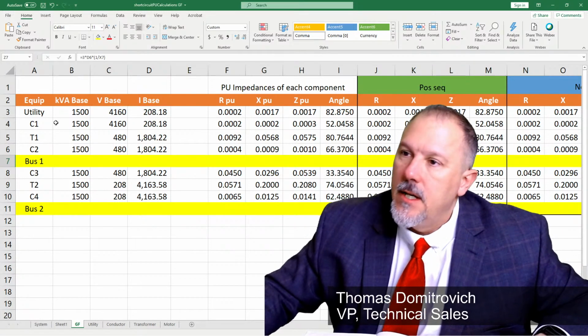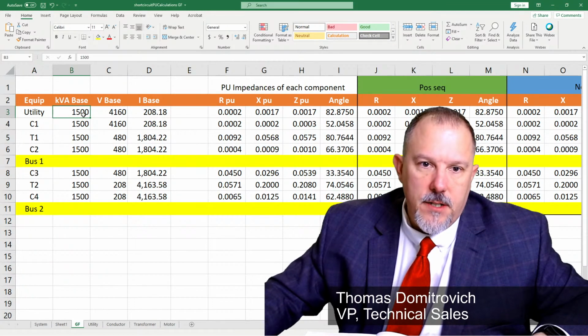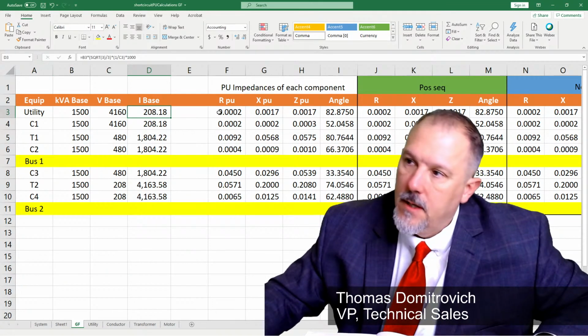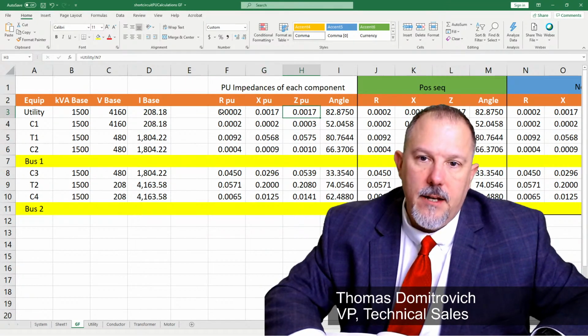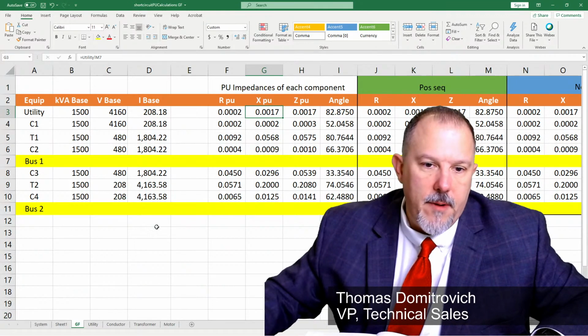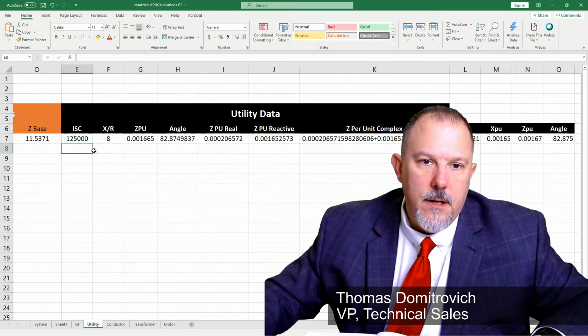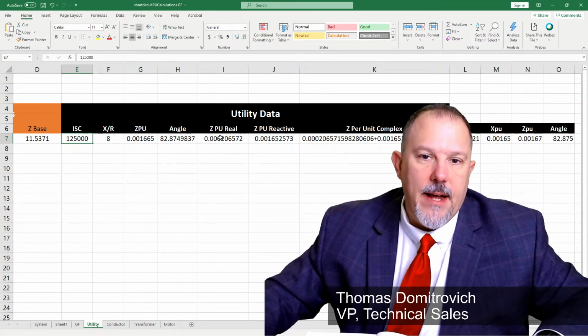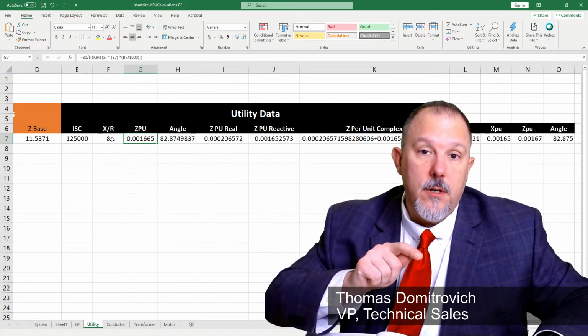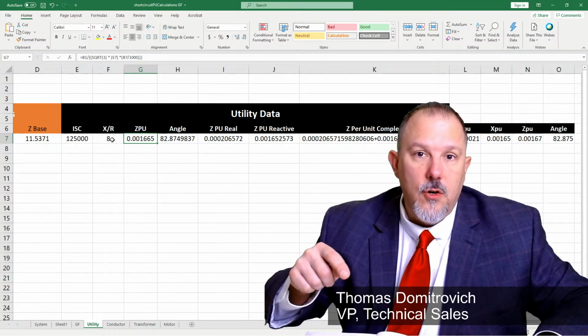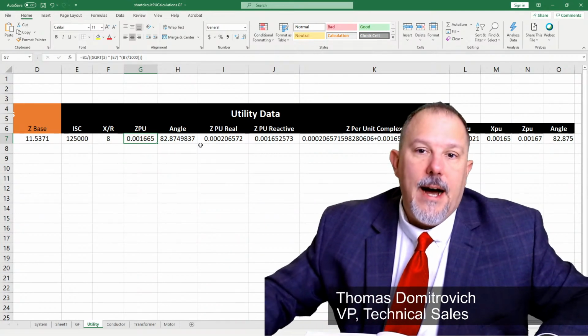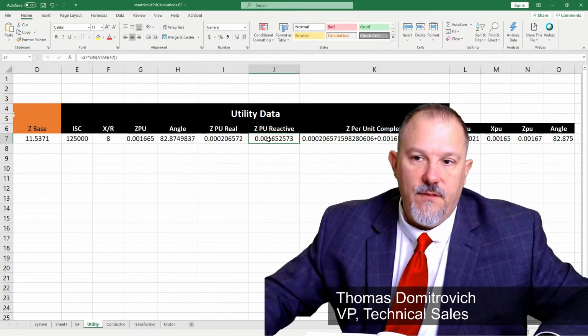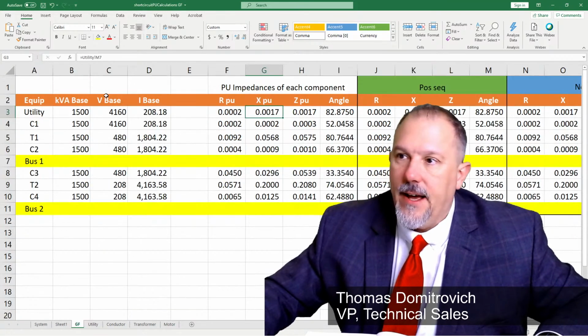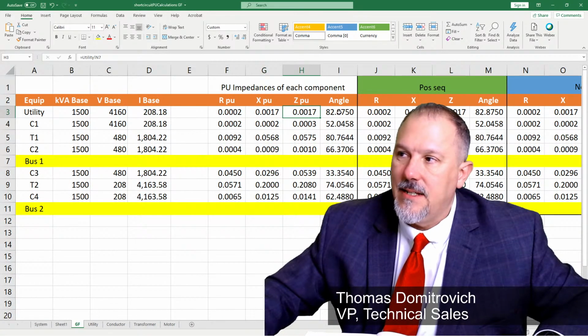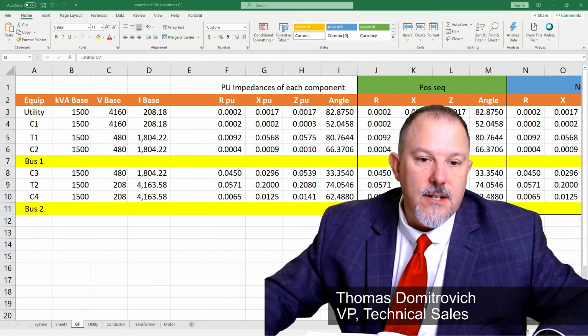So here's what I got. There's my utility. There's my KVA base, my voltage base, my I base. That's important. There's my R per unit of the utility and my X per unit. And you can see, remember, I have a utility tab. And this is where I have the equation. With the equation from the Beeman handbook, I calculate the Z per unit and the angle, because we know the angle since we're given an X to R ratio. I convert that into my real and reactive per unit values. And then I have that over here, my real and my reactive. I have my Z and my angle. And for the conductors, I have a conductor tab.